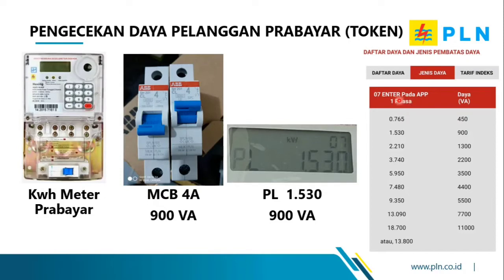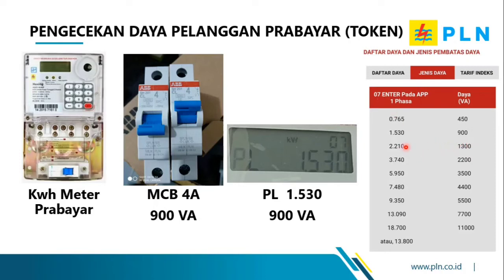Angka yang muncul pada KWH meter setelah menekan 07 enter itulah keterangan untuk informasi daya kontrak yang sesuai dengan daya PLN. Ketika kita tekan angka 07 enter pada KWH meter token atau listrik prabayar dan muncul angka 1.53, maka daya kontrak yang sesuai dengan KWH meter tersebut adalah 900 VA. Teman-teman atau elektrisan bisa membandingkan angka yang muncul — misalnya pada daya 1300 VA, ketika kita tekan 07 enter akan muncul angka 2.210.